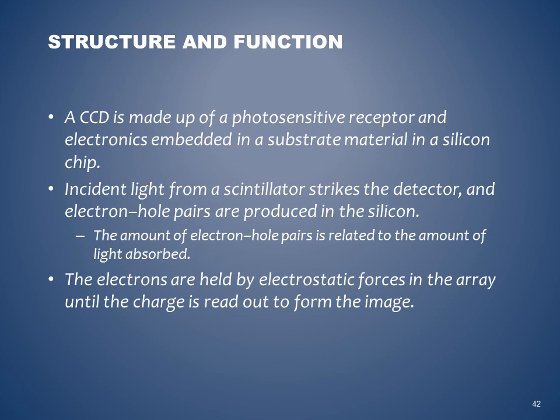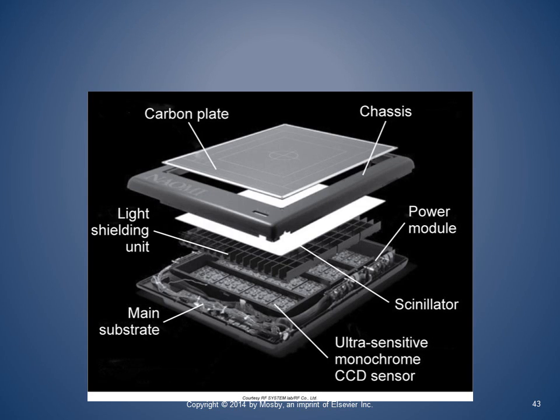Structure and function. A CCD is made up of a photosensitive receptor and electronics embedded in a substrate material in a silicon chip. Incident light from a scintillator strikes the detector and electron-hole pairs are produced in the silicon. The amount of electron-hole pairs is related to the amount of light absorbed. The electrons are held by electrostatic forces in the array until the charge is read out to form the image.